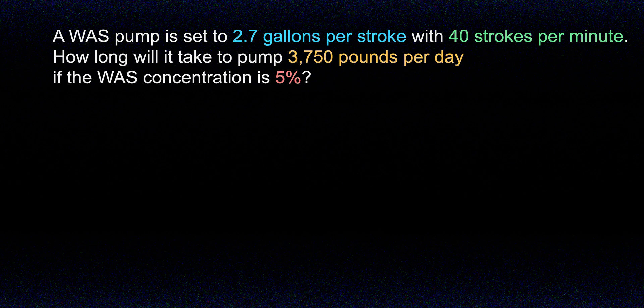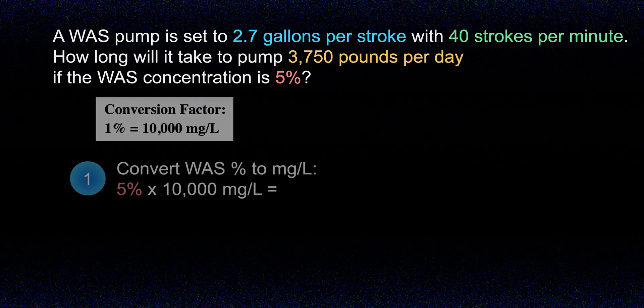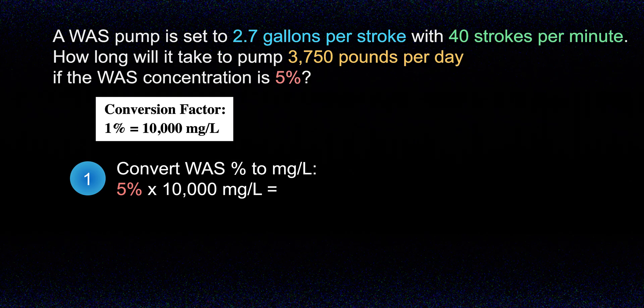In this question, we are asked how long it will take to pump 3,750 pounds of solids contained in the waste-activated sludge per day, and the answer needs to be in minutes. We are given that the pump moves 2.7 gallons per stroke and works at 40 strokes per minute, and the WAS concentration is 5%. The very first step is to convert the sludge concentration from a percentage into milligrams per liter. Remember that 1% equals 10,000 mg/L, so our 5% sludge concentration equals 50,000 mg/L.